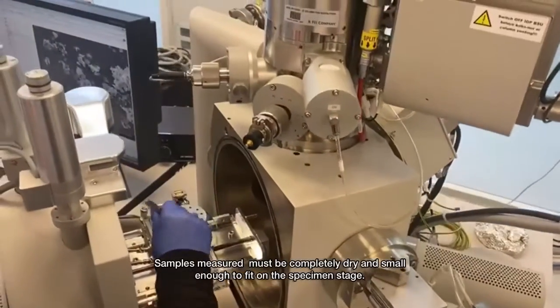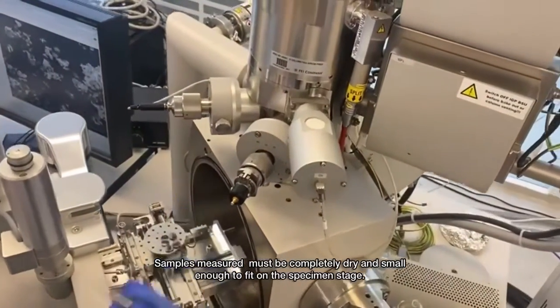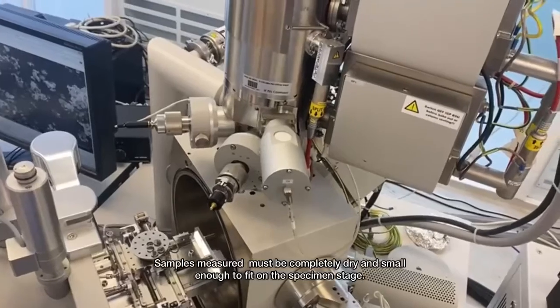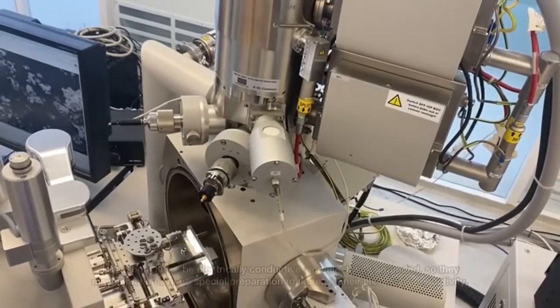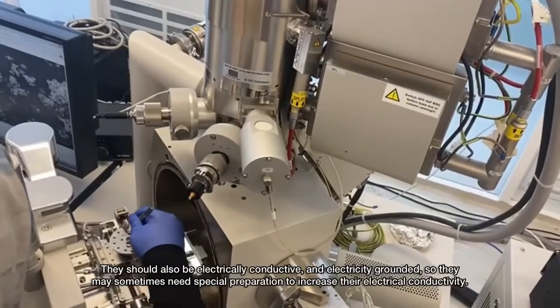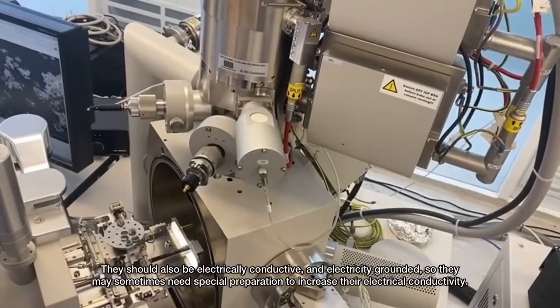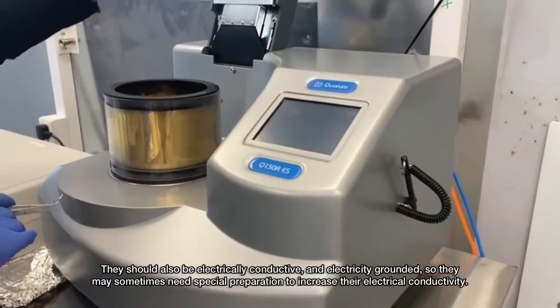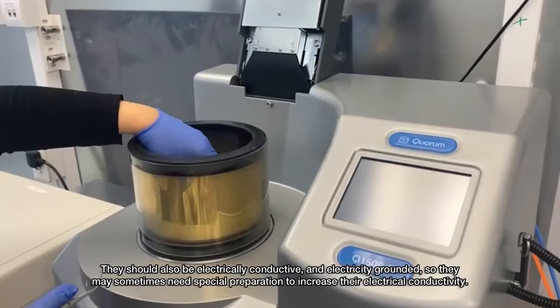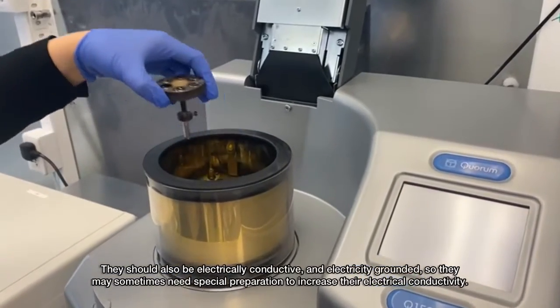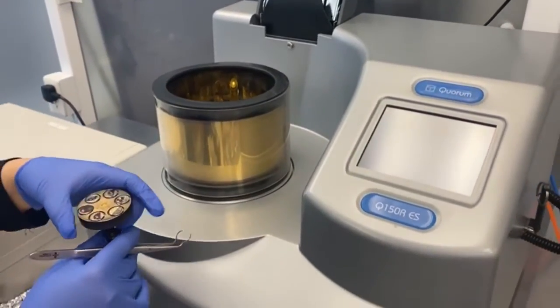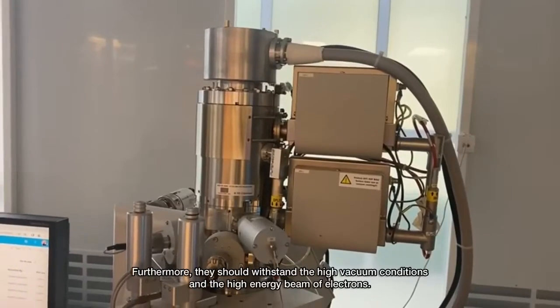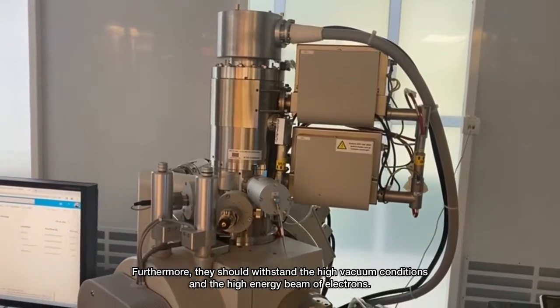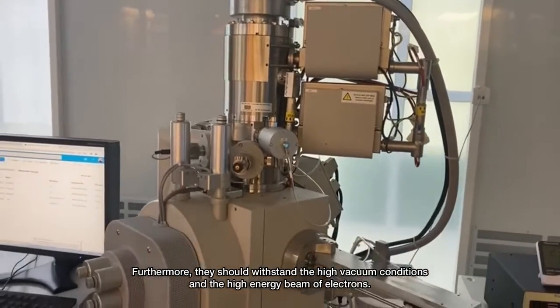Samples measured must be completely dry, and small enough to fit on the specimen stage. They should also be electrically conductive, and electrically grounded, so they may sometimes need special preparation to increase their electrical conductivity. Furthermore, they should withstand the high vacuum conditions and the high energy beam of electrons.